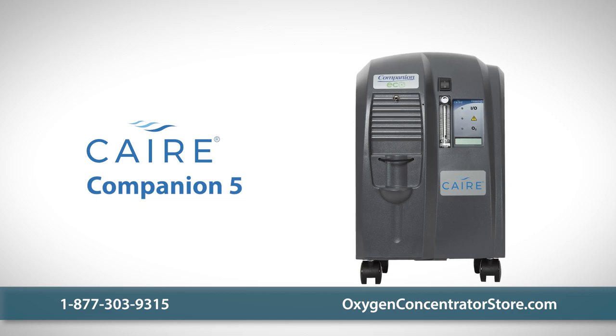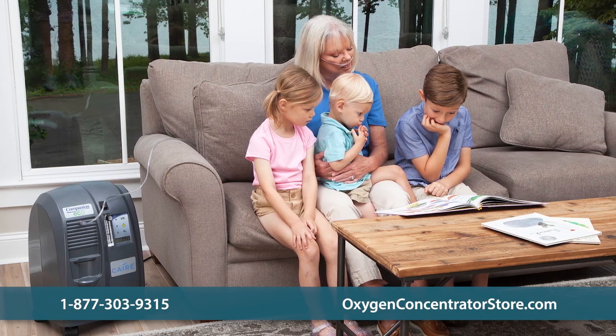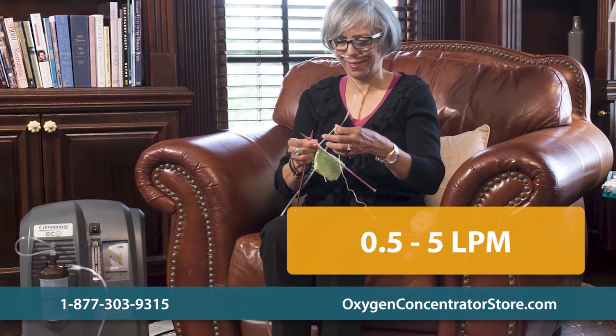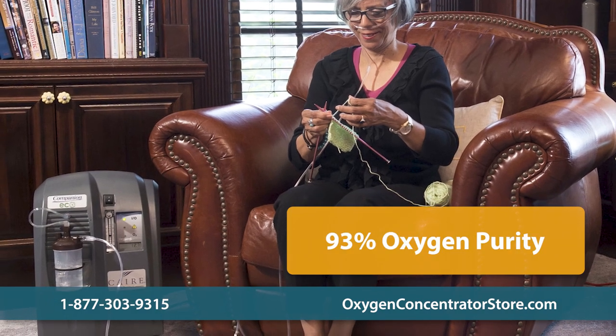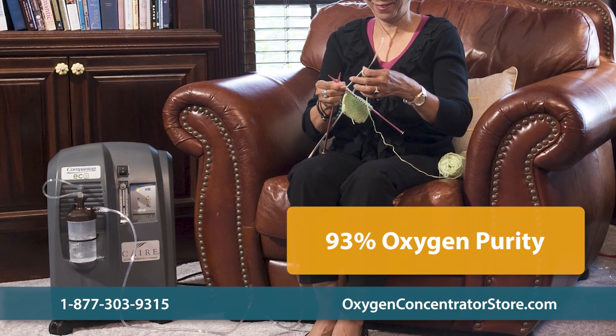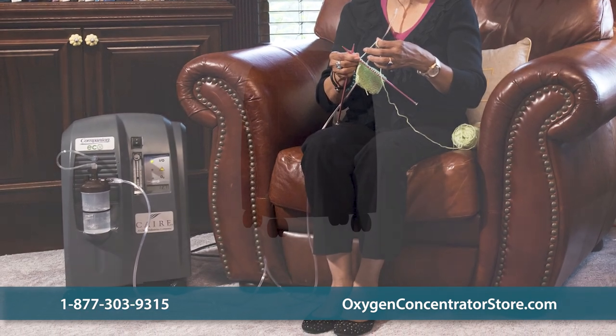The CAIRE Companion 5 stationary oxygen concentrator is an ideal solution for receiving oxygen therapy at home. The unit's oxygen flow settings range from 0.5 to 5 liters per minute with an average oxygen purity of 93%, making it perfect for users who need a low dosage of continuous flow or only need oxygen therapy for a few hours at a time.